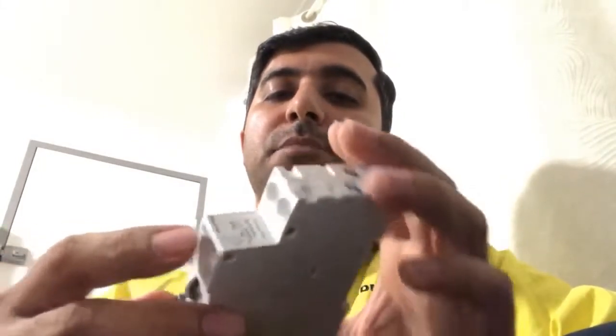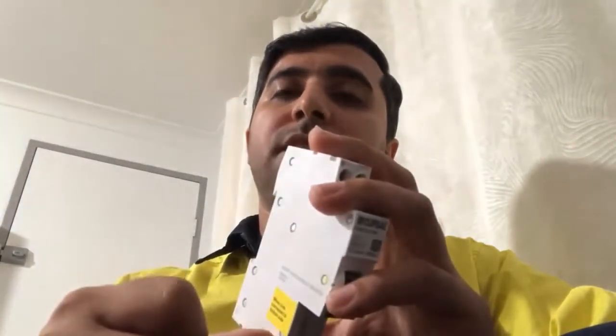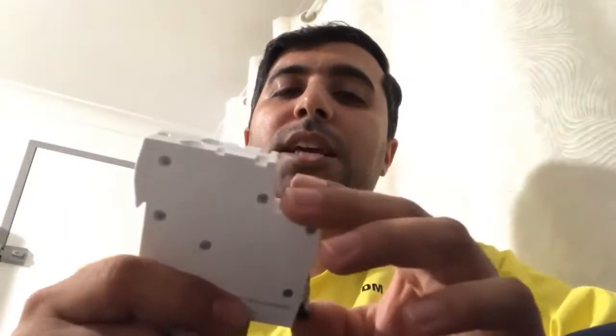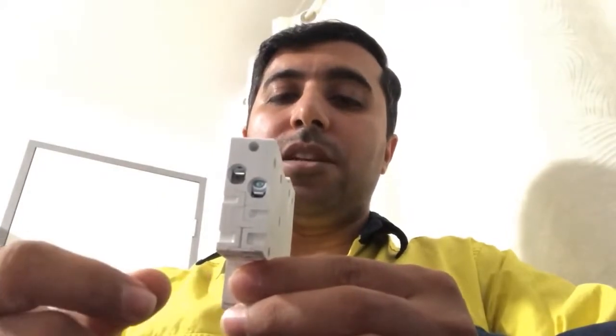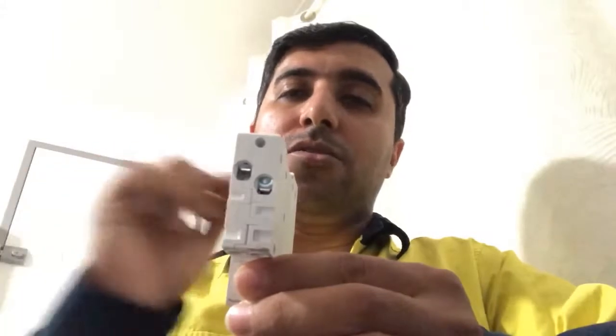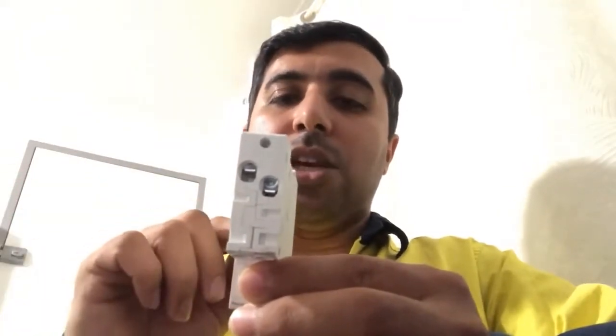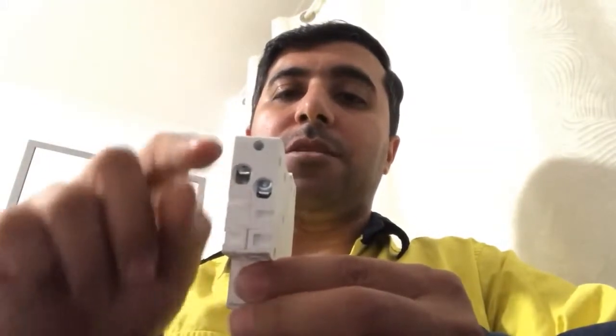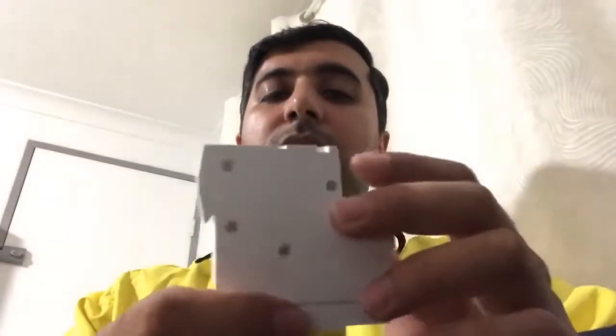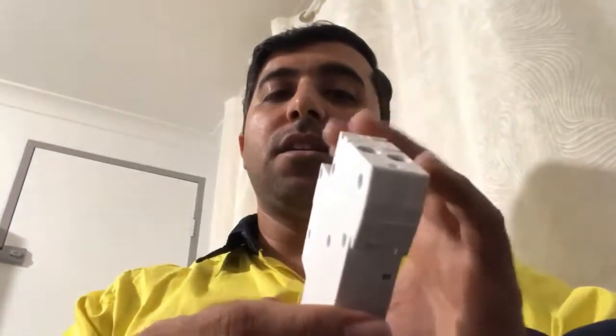What it does is that it has a mechanism inside of it that can detect electrical leakage. By that I mean it constantly monitors the current flowing through the active wire and coming back through the neutral. So if there is any kind of leakage from either the active or the neutral to the earth, for example via the metal body of an appliance, or through your body or something, it can be detected. So if the current going out from the active wire is not exactly the same as the current coming back from the neutral, the device can detect that and it shuts the circuit. It shuts the circuit by tripping the switch. The sensitivity of this device is about 25 milliamps and above. So anything in that range or more can be detected quickly by this device, and it is going to shut the circuit.